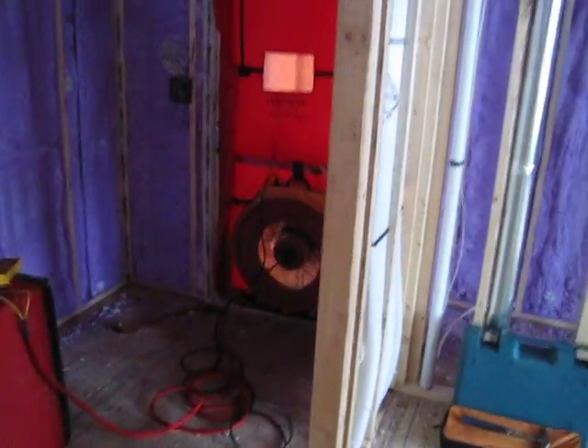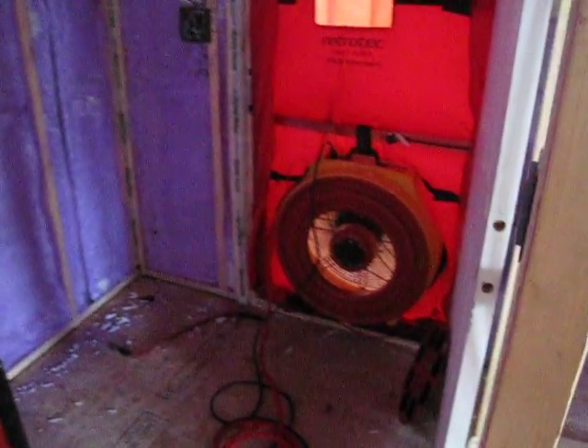What we have here is a blower door operating to depressurize the house, and this allows us to check for air leakage. If you have a look at the manometer here, we're at about minus 49 — we like to set it at about minus 50 — which is drawing cold air in from the outside.